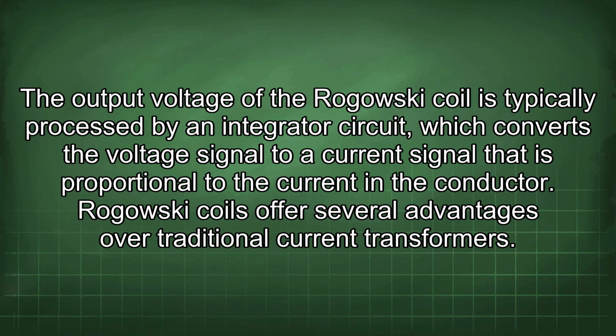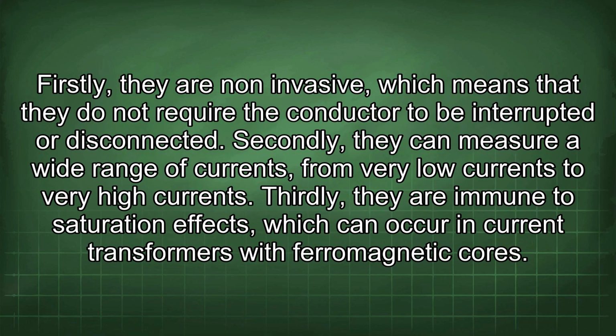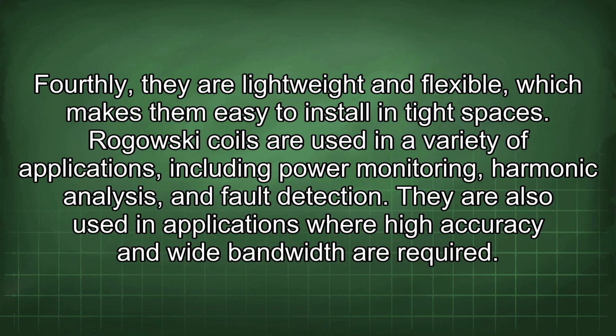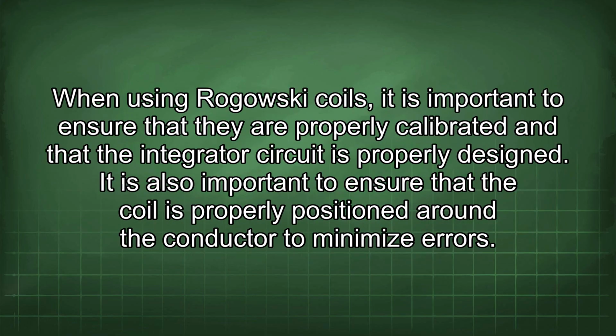Rogowski coils offer several advantages over traditional current transformers. Firstly, they are non-invasive, which means that they do not require the conductor to be interrupted or disconnected. Secondly, they can measure a wide range of currents from very low currents to very high currents. Thirdly, they are immune to saturation effects, which can occur in current transformers with ferromagnetic cores. Fourthly, they are lightweight and flexible, which makes them easy to install in tight spaces. Rogowski coils are used in a variety of applications, including power monitoring, harmonic analysis, and fault detection. They are also used in applications where high accuracy and wide bandwidth are required. When using Rogowski coils, it is important to ensure that they are properly calibrated and that the integrator circuit is properly designed. It is also important to ensure that the coil is properly positioned around the conductor to minimize errors.